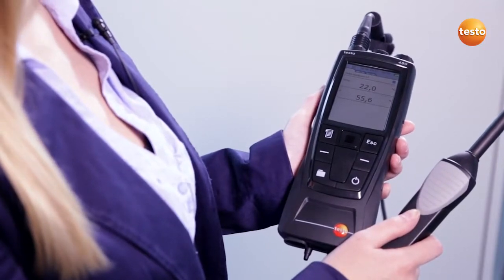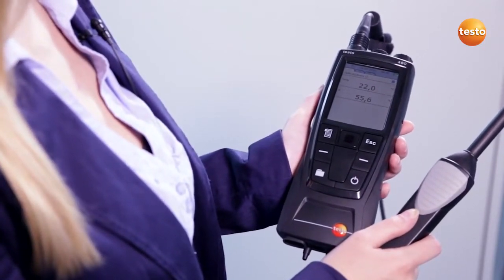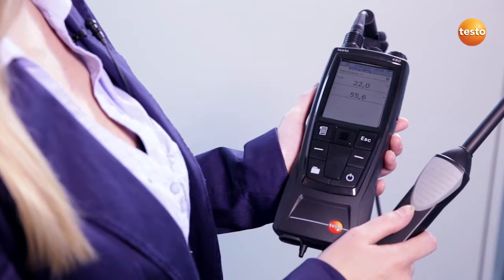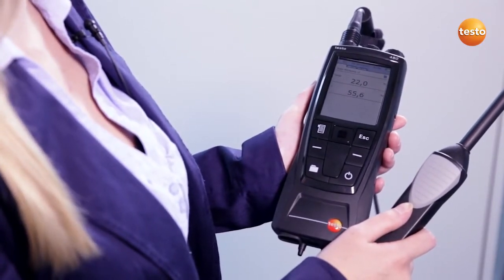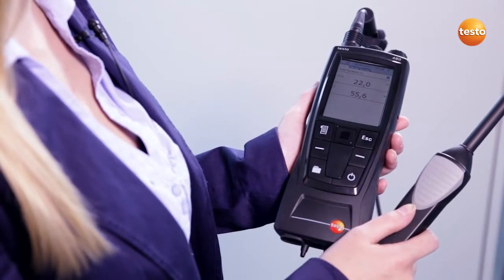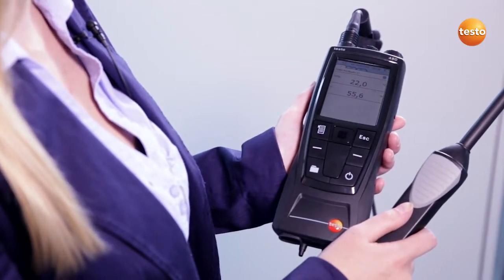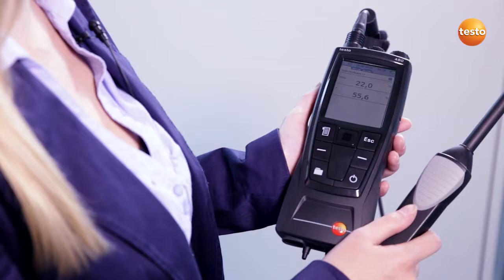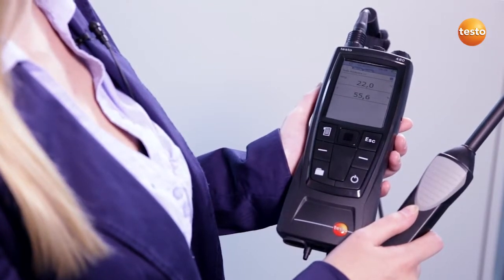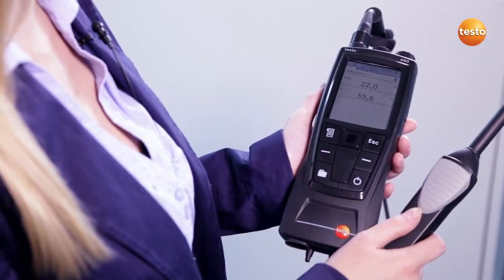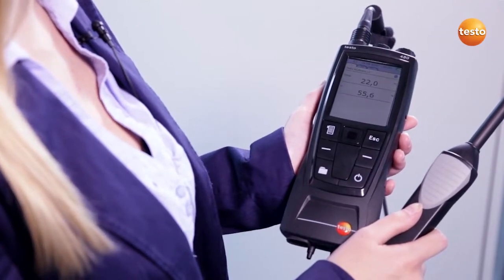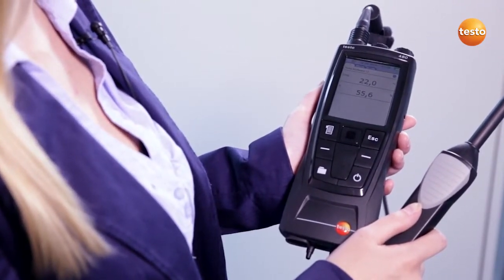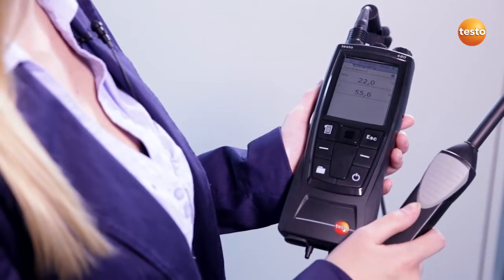In this office, I've measured a temperature of 22 degrees centigrade and a relative air humidity of 55.6%. The recommended values for offices are between 22 and 24 degrees centigrade and 40 to 60% humidity. If the measured values here already showed a considerable deviation from the comfort range, this would be due to an incorrectly adjusted ventilation system.